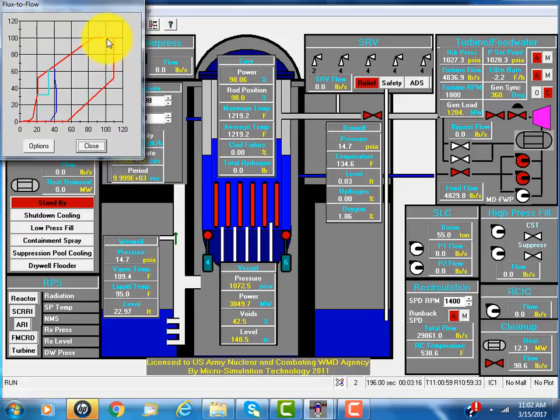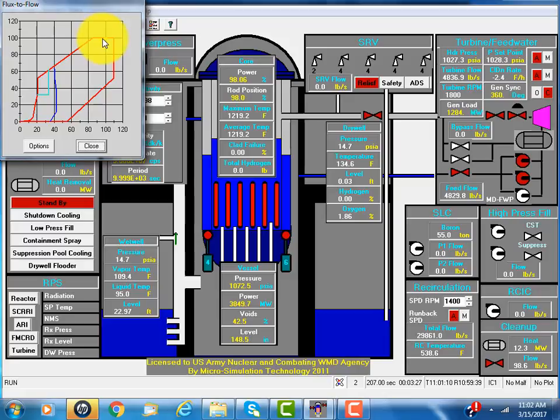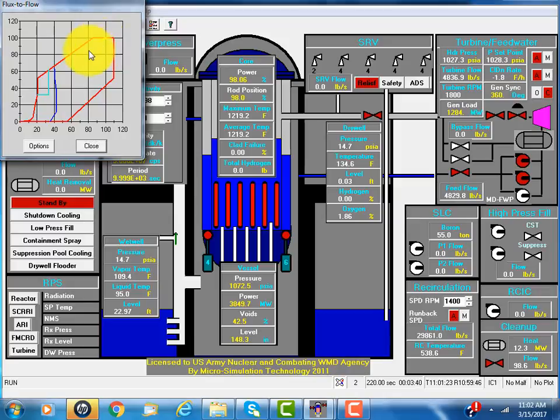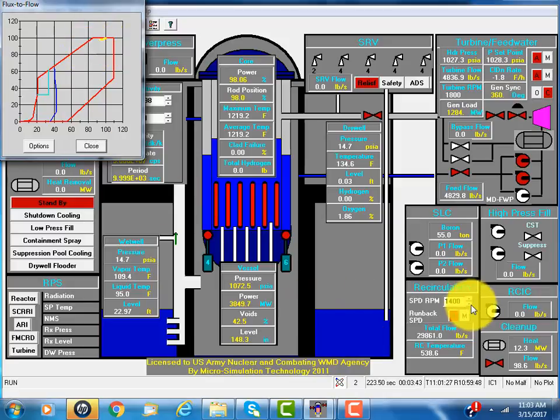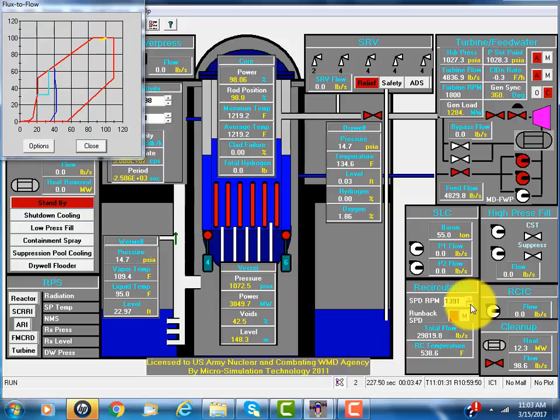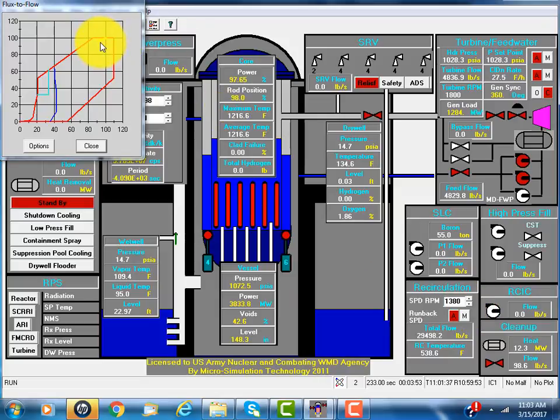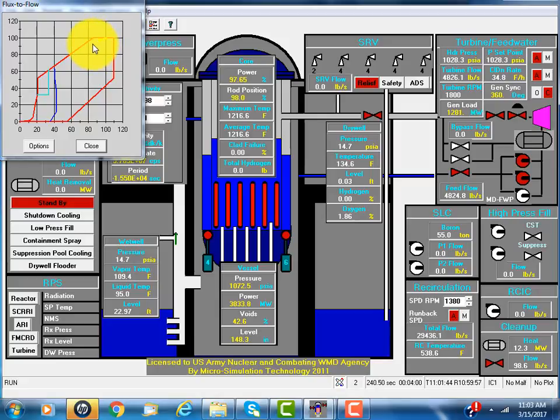By reducing the recirculation flow, there are more voids and lesser power. The yellow operating point is moving to the lower left. If we do more, you'll see that yellow dot move further, lower power.